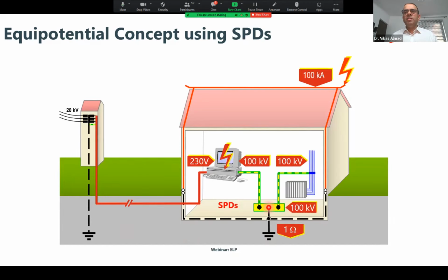potential across the earth. Everybody knows that a fault current creates a GPR, and this GPR creates a potential difference, which then creates a big current, and this current is depending upon this strike. And there could be the current coming as a surge also inside the equipment bidirectional. And what we have to do is we have to give a path to this current so that this voltage difference is not there. So we cannot short line an earth, we cannot short line a neutral. We have to create equipotential bonding.